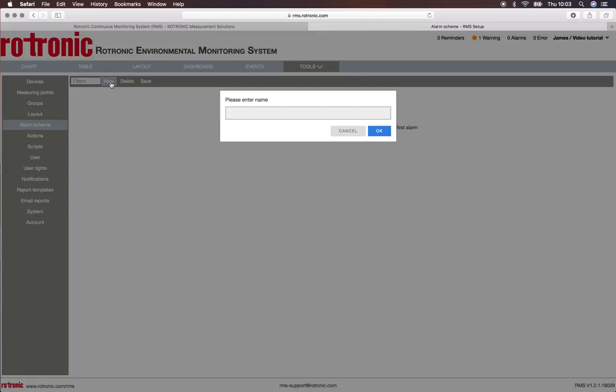If we have 20 different measurement devices for temperature, we can set up one alarm under alarm scheme and put this alarm scheme onto each signal. It's much faster, especially if we need to change it.